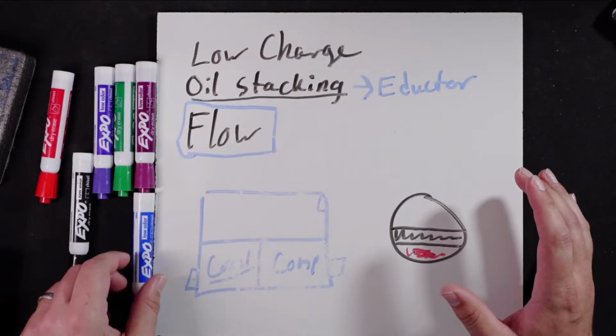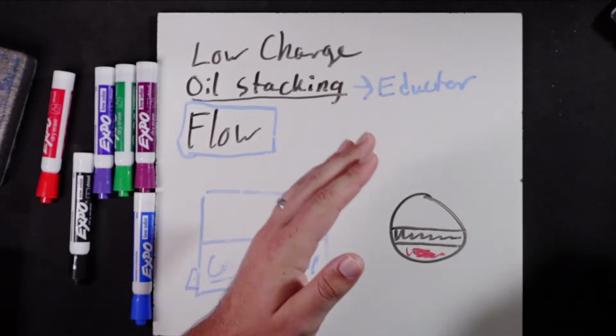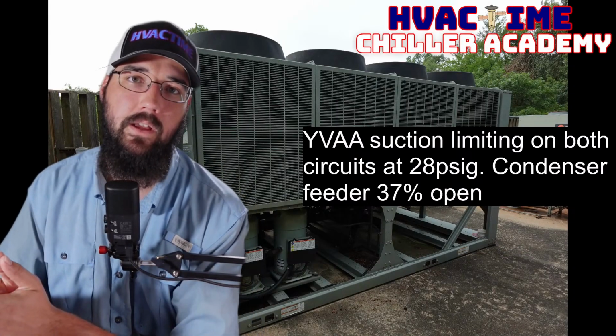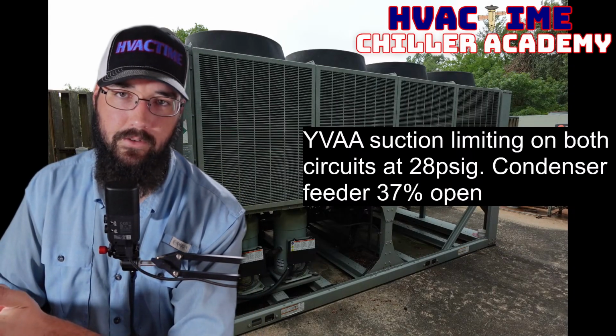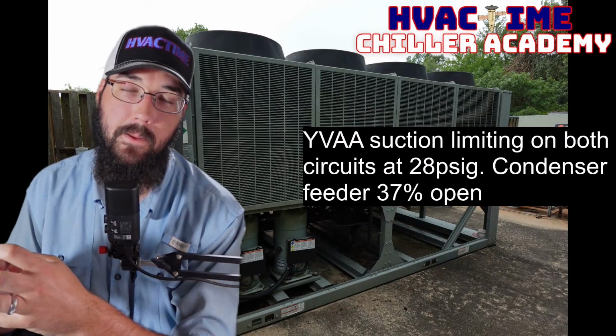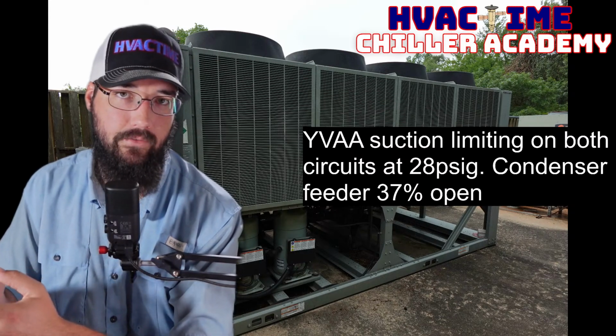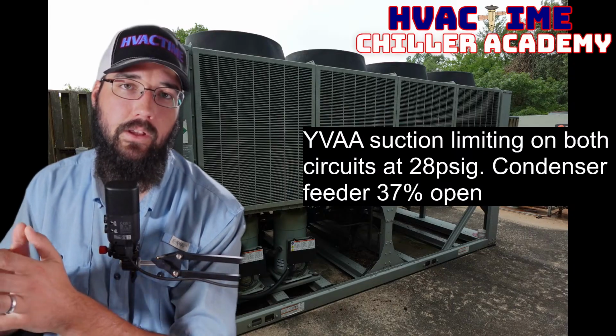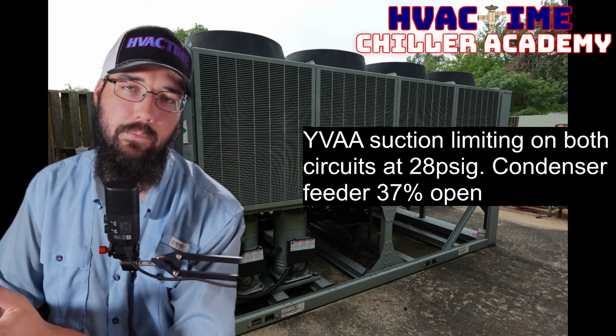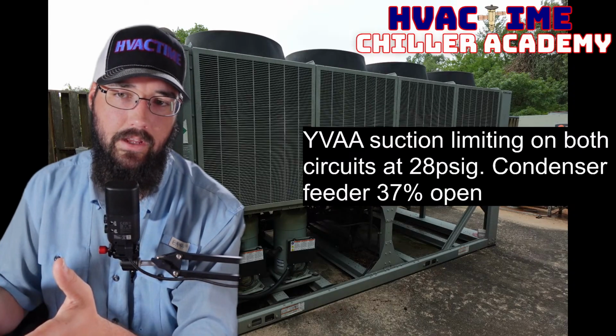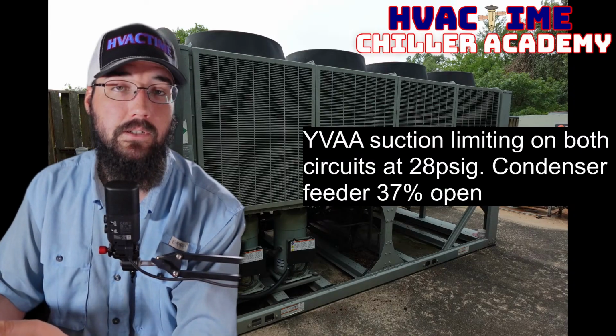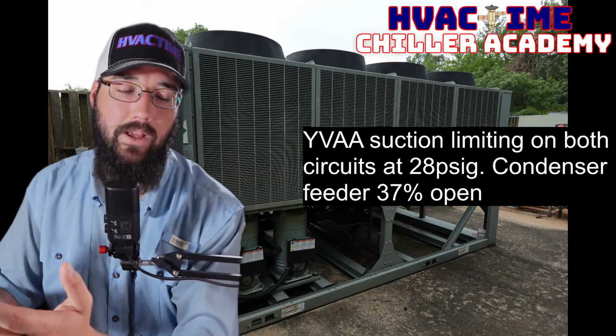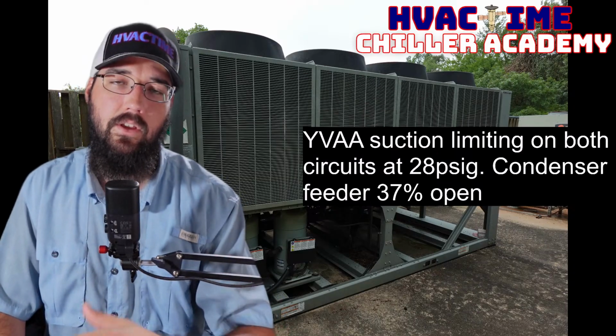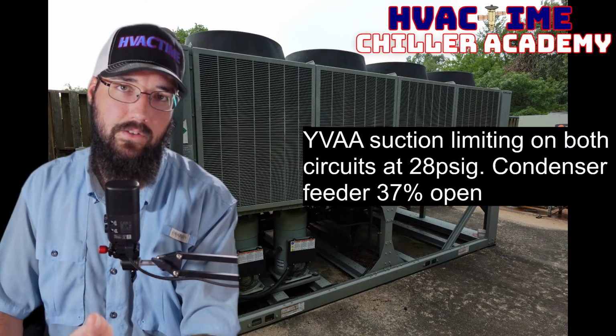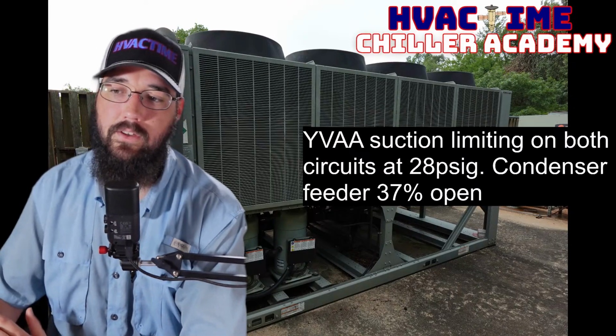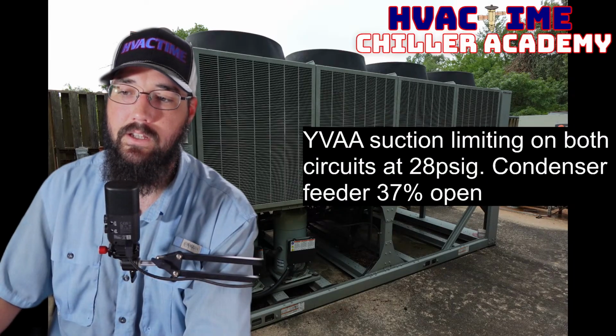In terms of flow, it is very likely going to be the most probable cause here. That's the baseline I'm getting to. I don't know that you have enough flow. Too little flow, you don't have enough heat getting into the evaporator, and that is causing a suction limiting problem. And if we increase the flow after we've verified the rest of this, I would expect to see these conditions improve.